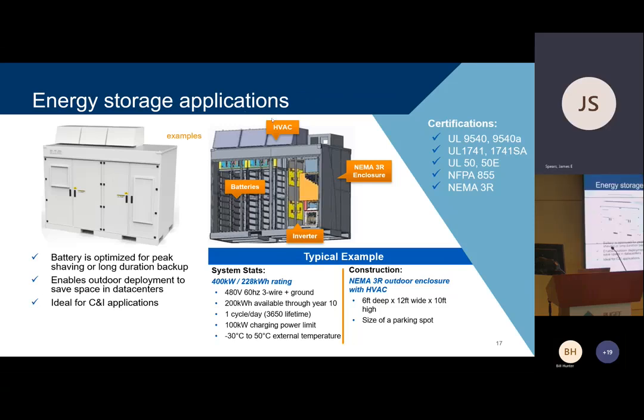So here's some applications of what that looks like. This is a peak shaving device, and it goes outdoors in this case, and it has a power converter. Looking at the open graphic on the right, it has an inverter system based on one of our UPS products, and most of it is space for lithium-ion batteries. These are also made by Samsung, but they are lower C-rate batteries intended for longer, slower discharges, and the NEMA 3R enclosure with lots of air-cooled air conditioning and HVAC on the top of the cabinet.